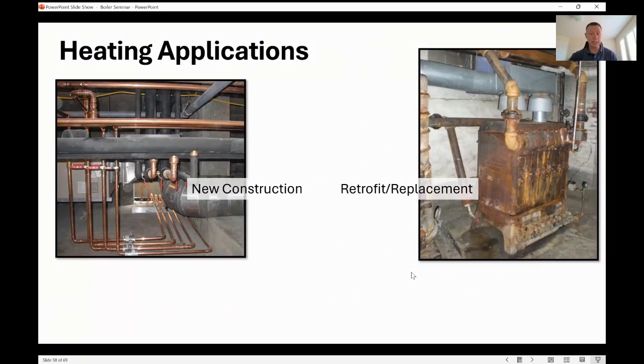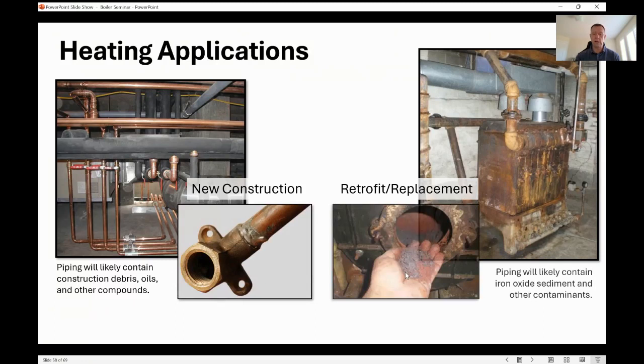Retrofit especially, because I don't know why. There's magnetite, there's a whole bunch of crap in these pipes. It's operated fine through the years. It hasn't taken down the existing boiler there. But as soon as you replace that boiler, you rattle the pipes or something happens, all the crap just comes out of the pipe. It always does. So be conscious of it and deal with it. So, 6 months later, there's not a non-warrantable failure happening there.